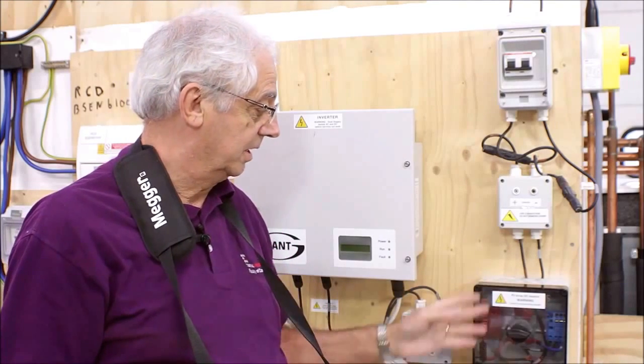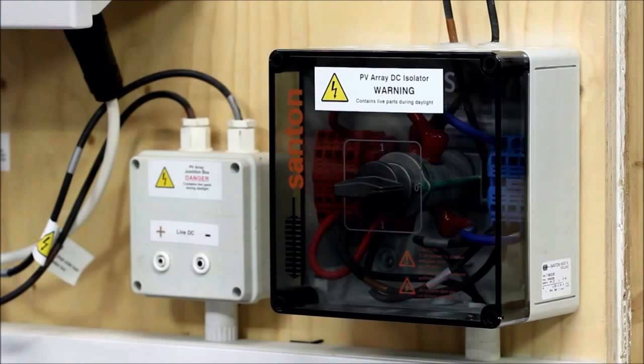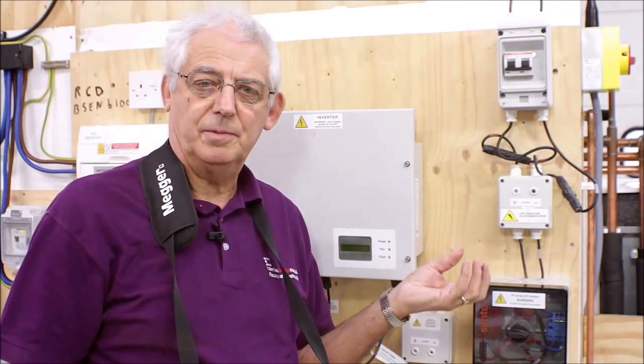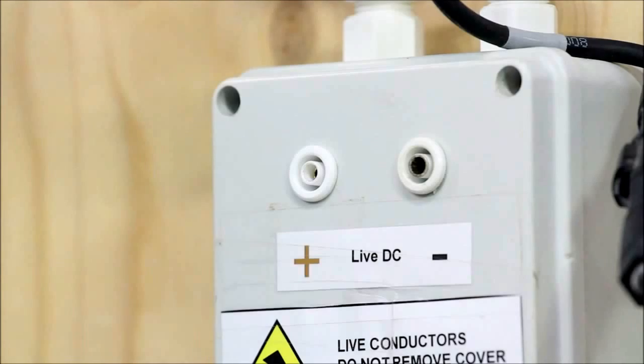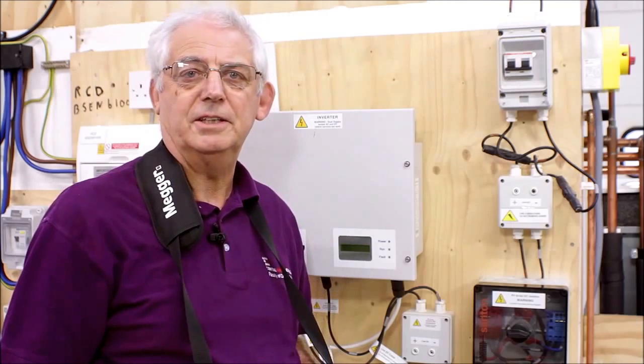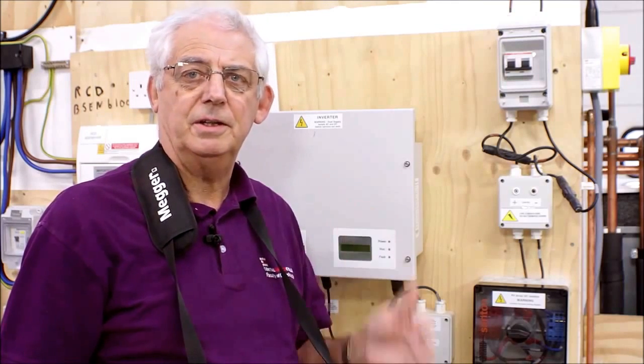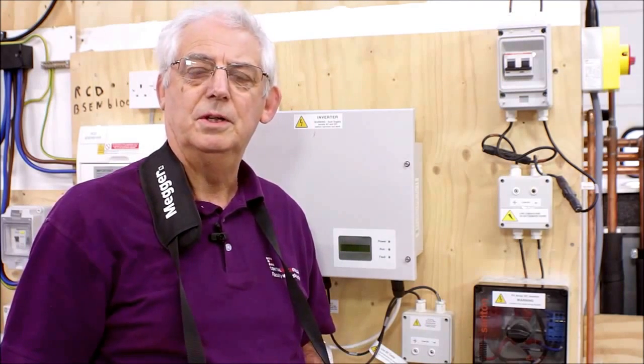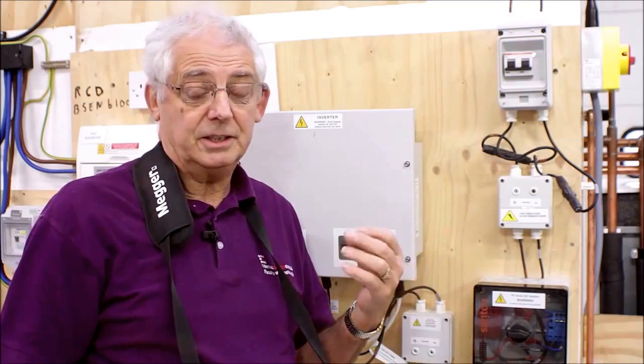The PV isolator that we use for training is here, and we've got a little plate there with our connections that we can use to take different values of readings. The first test we're going to do is an insulation resistance test. So our panels are outside, everything's fully operational, and it's going to be operational because you can't isolate a PV panel once it's exposed to sunlight. The only way you can do it is disconnect it.